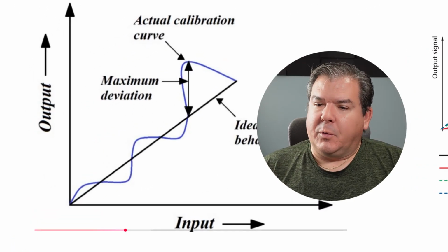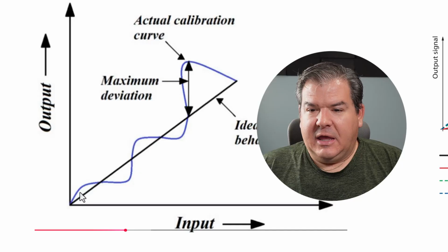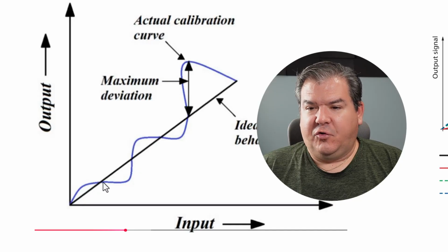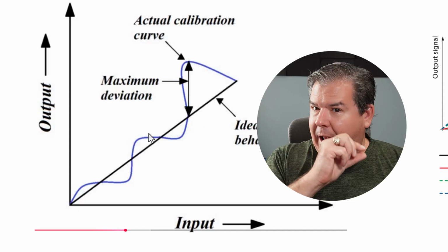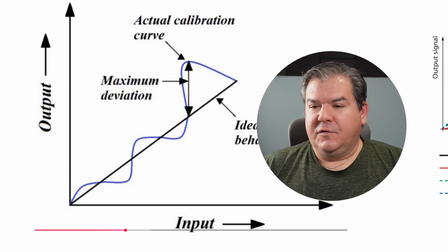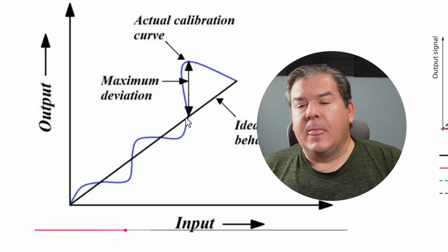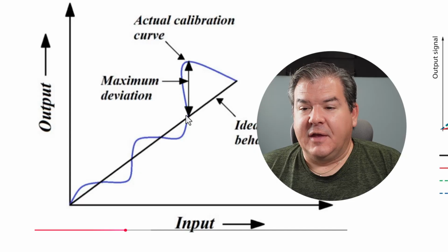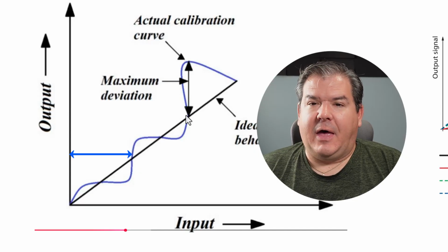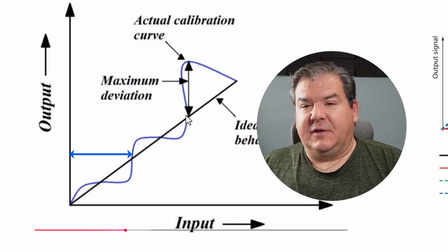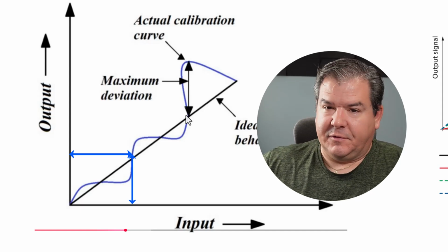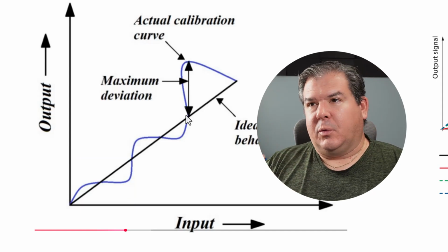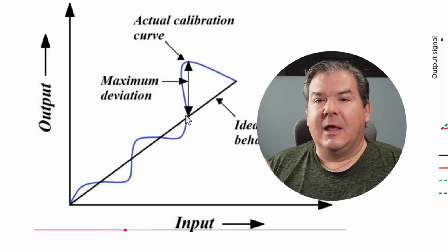But what you can do, if the repeatability is there, it will follow this trace, this curve within that repeatability error, and you can use a lookup table in a PLC or in a computer processor, whatever it is, that says, all right, I'm getting this value out of my sensor. That actually is equal to this absolute value or this relative value in space even. So the repeatable nonlinearity can be dealt with.